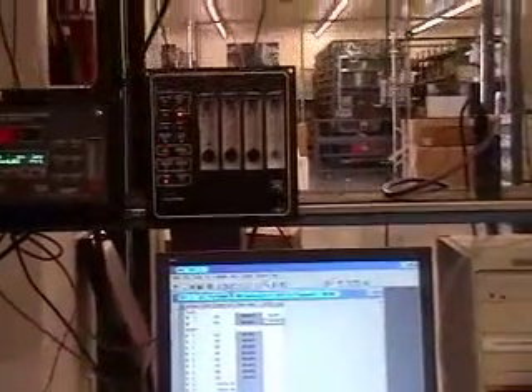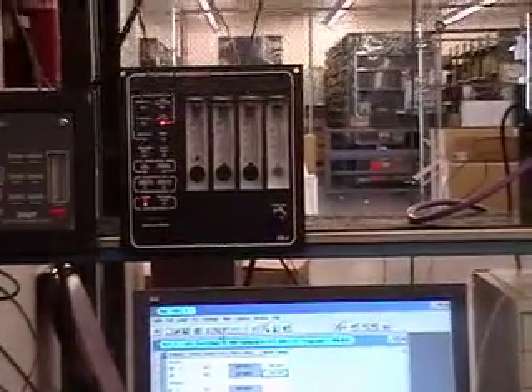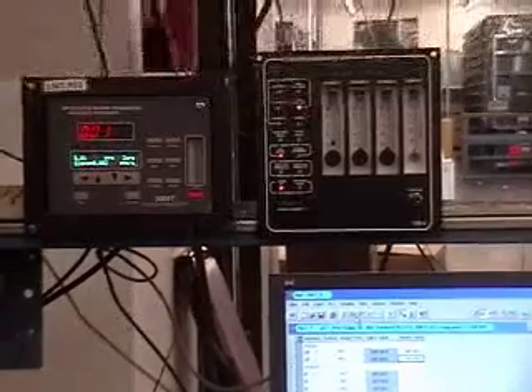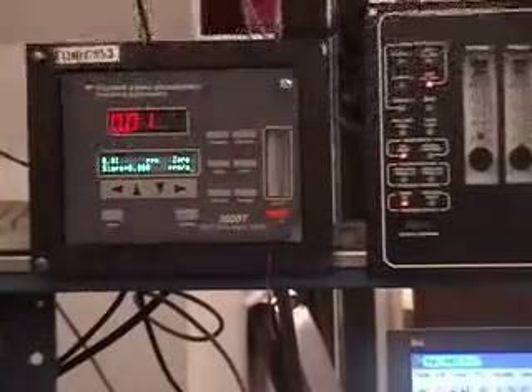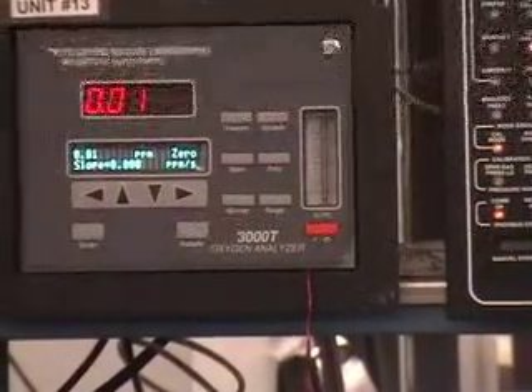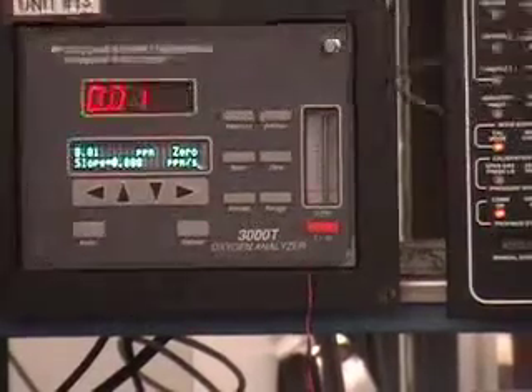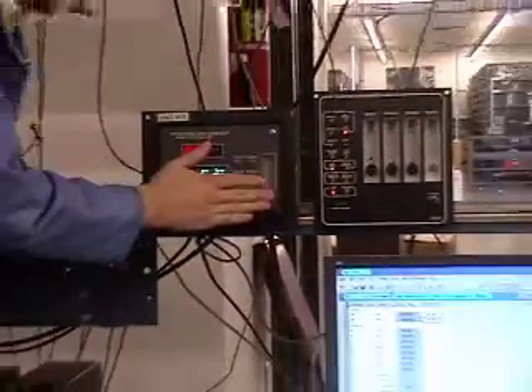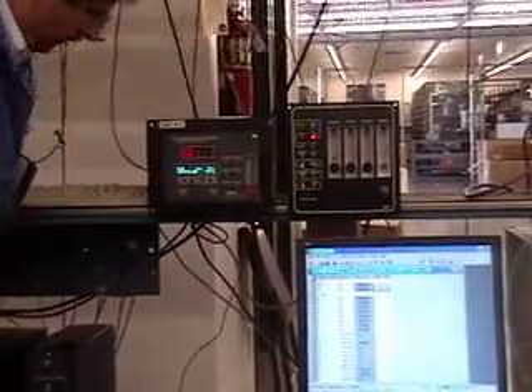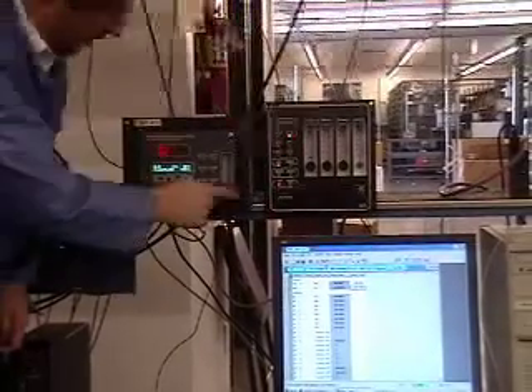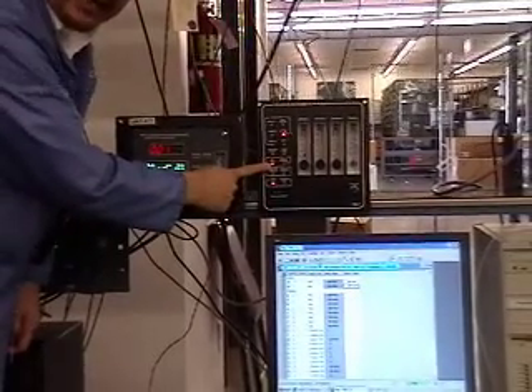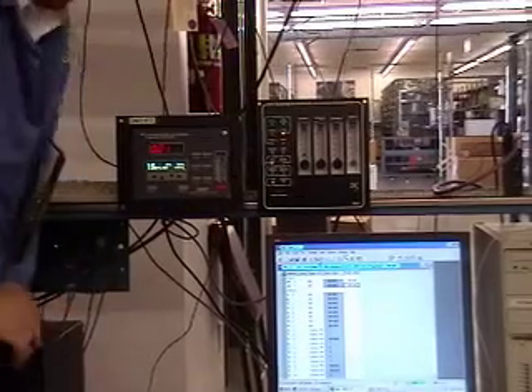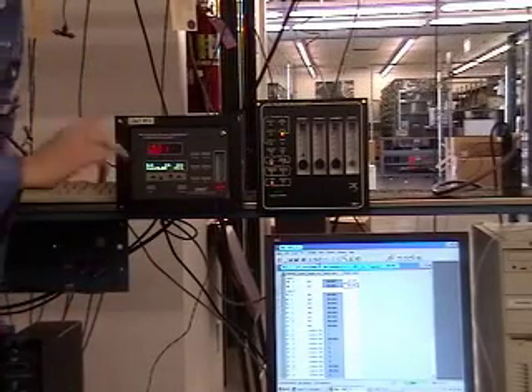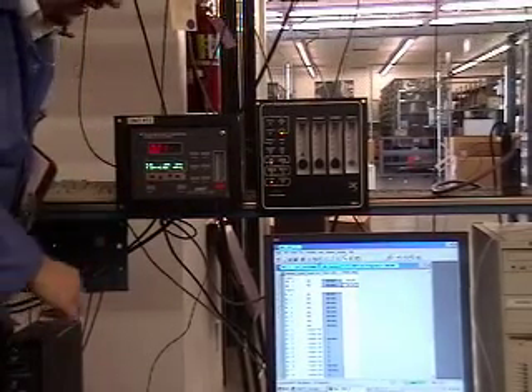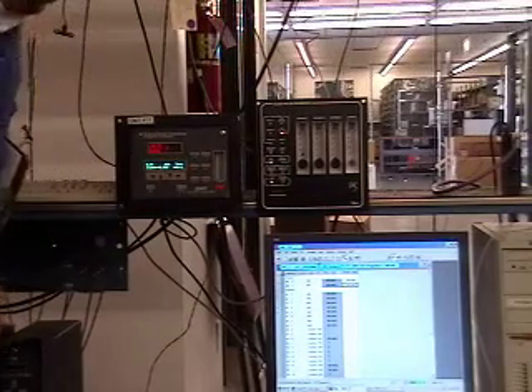And we see the local gas open. The analyzer is now in 0 mode. And now that it's in 0 mode, I'm going to return back to valve number 1 and send that command so it's queued, so that when it's finished zeroing, it will go back to sample 1. So the analyzer is in 0 mode, and you can see the cal mode light coming on. That means the analyzer is zeroing. It knows, by looking at the RS-232 data, that the analyzer is zeroing.